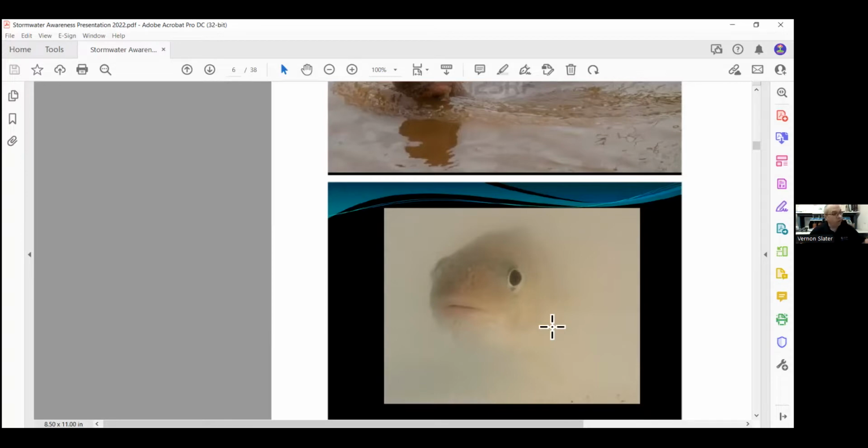Turbidity is a general term used to describe the cloudiness or dirtiness of a water sample. The turbidity of a given sample is determined by passing a light through a sample, measuring the reflective or scattered light in that sample. It is measured using a turbidimeter like the Hach 2100Q, the Hach 2100P, the Micro TOL 2 turbidimeter inline. Any of those turbidimeters can measure this. The measurement unit is a nephelometric turbidity unit, or just NTU. The higher the NTU, the dirtier the water. Turbidity is a good measurement of a water body's health.